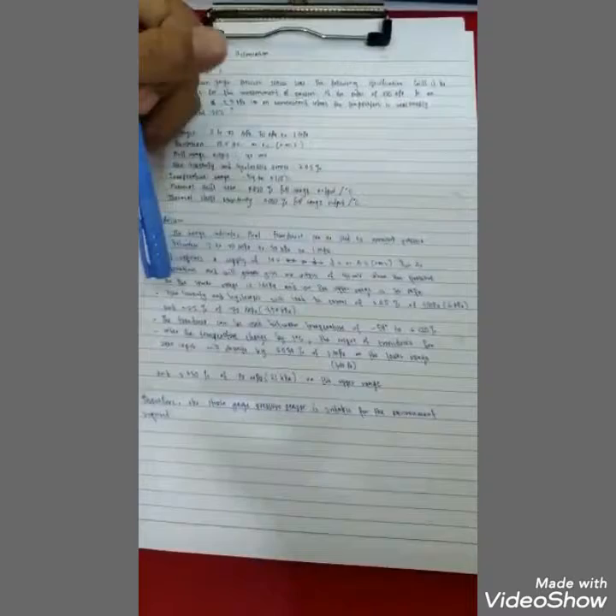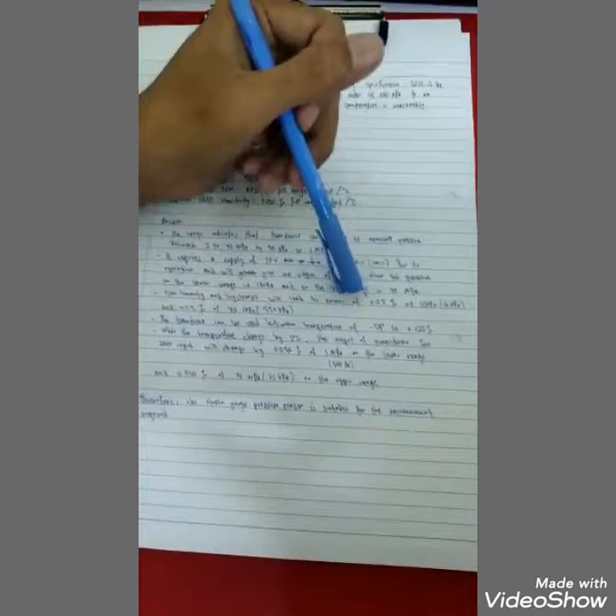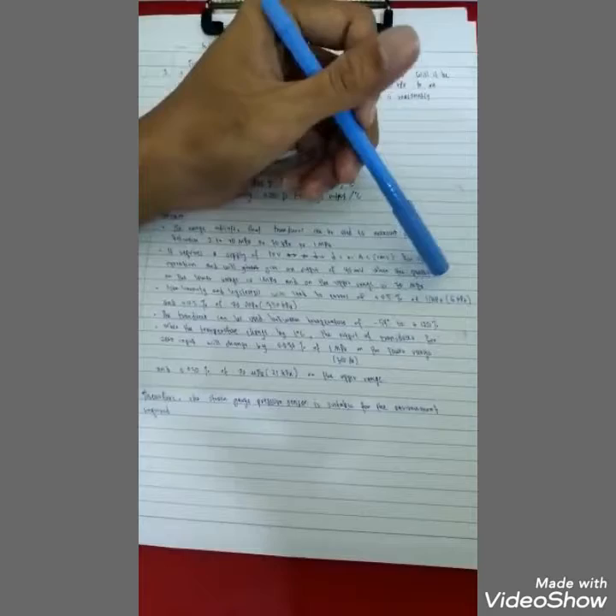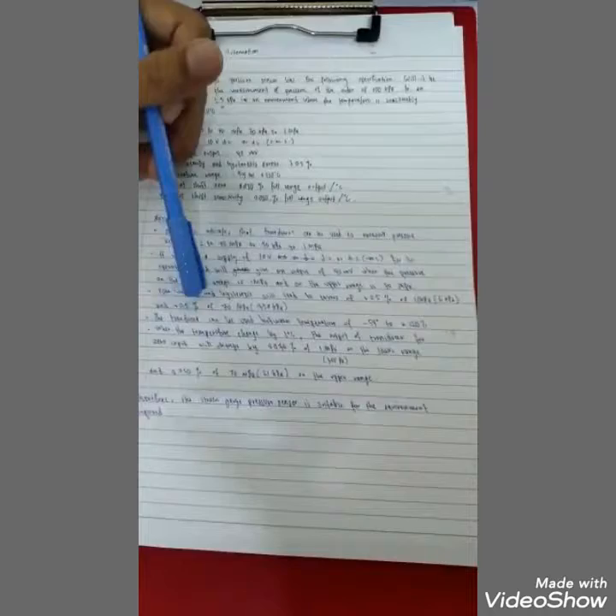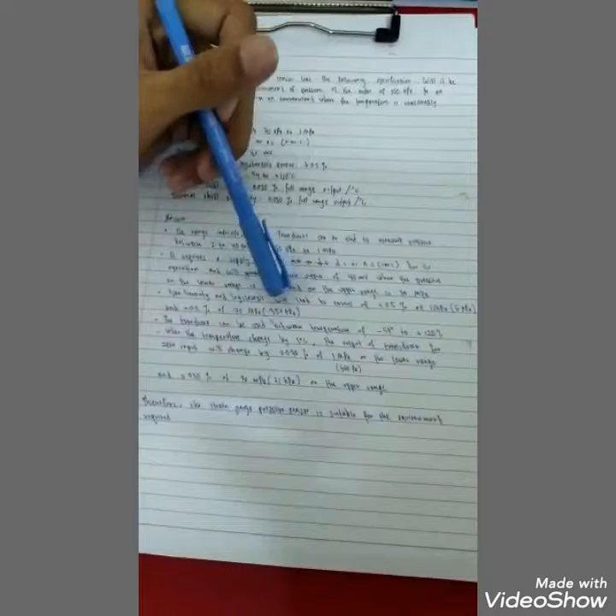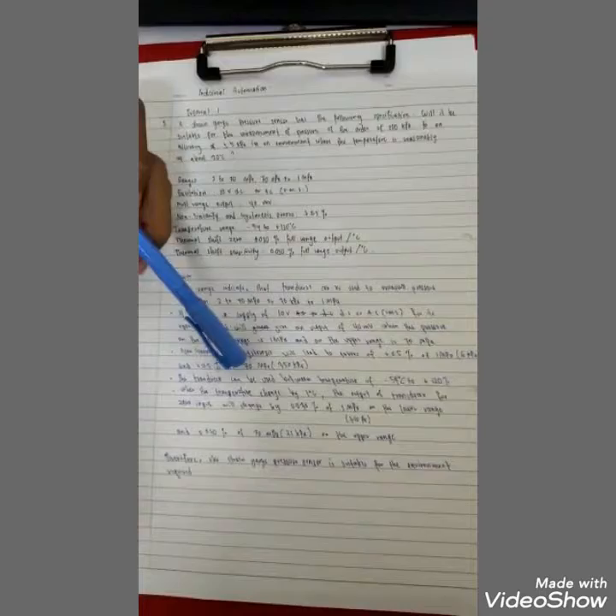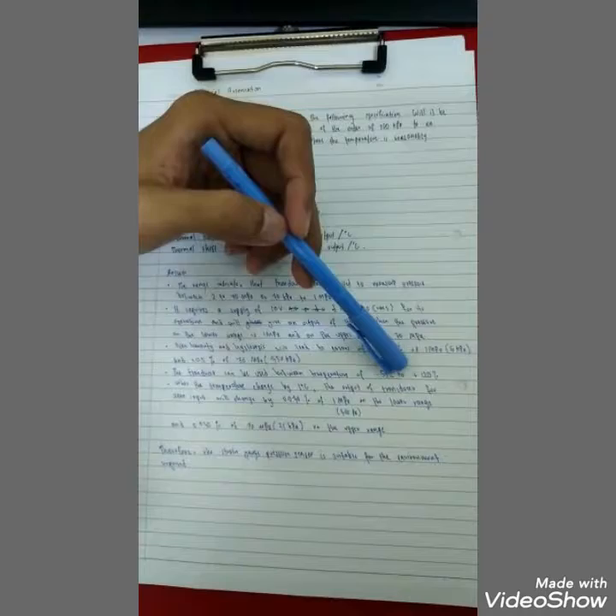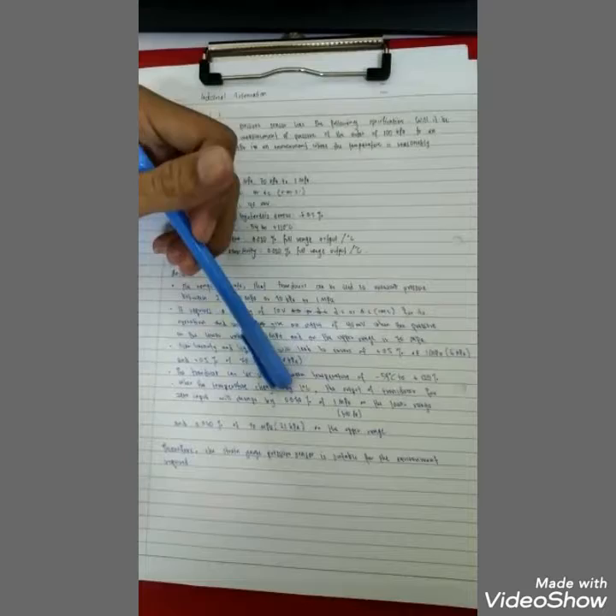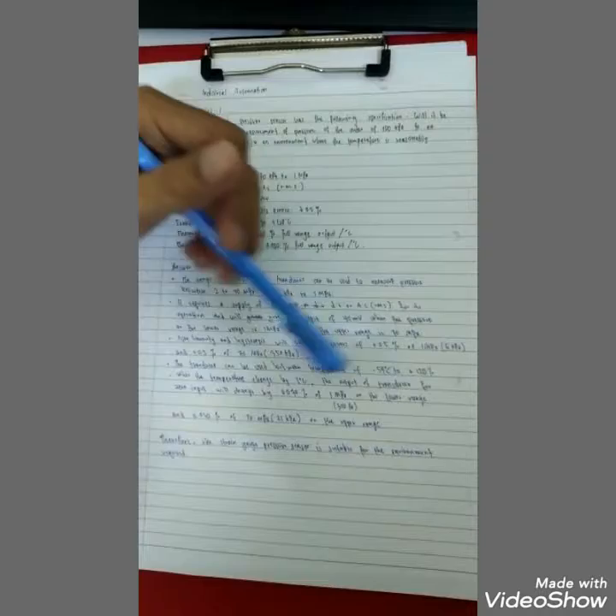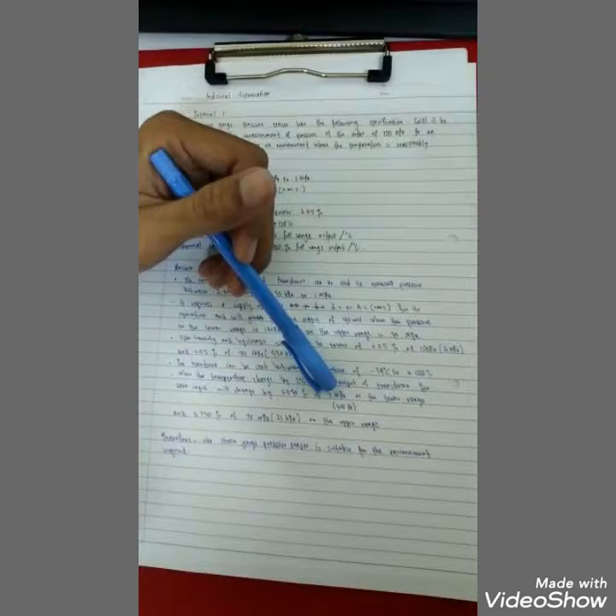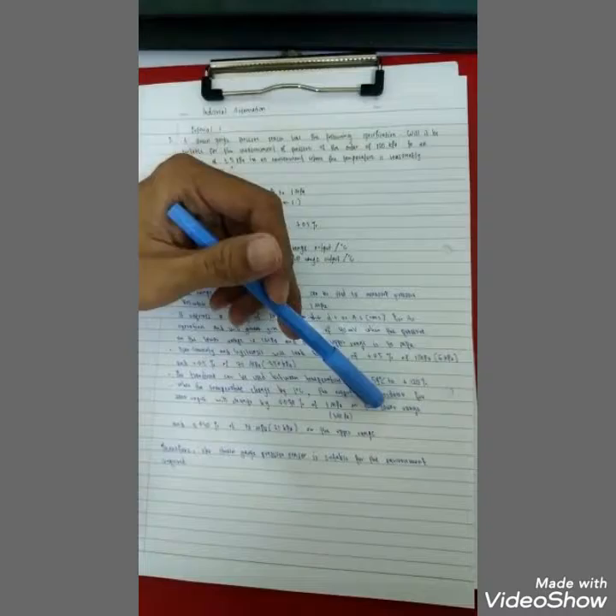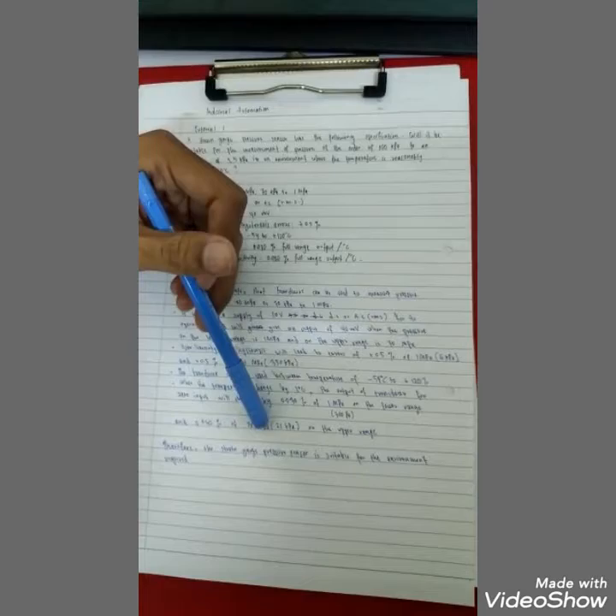Non-linearity and hysteresis will lead to an error of plus or minus 0.5% of 1 MPa, which is 5 kPa, and plus or minus 0.5% of 70 MPa, which is 350 kPa. The transducer can be used between temperatures of negative 54 degrees Celsius to 120 degrees Celsius. When the temperature changes by 1 degree Celsius, the output of the transducer for zero input will change by 0.03% of 1 MPa, which is 300 Pascal in the lower range, and 0.03% of 70 MPa, which is 21 kPa on the upper range.